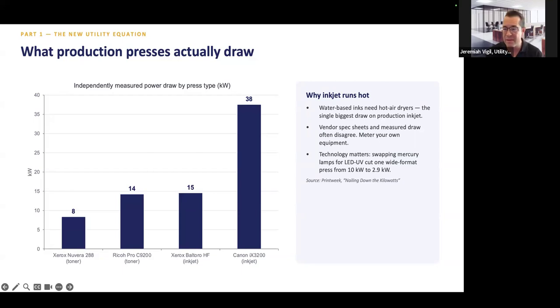On the right side, we have inkjet ones, a Xerox and a Canon. The Canon, based on the type of machine, is pulling more than double what the Xerox or even the toner machines like the Ricoh and the Nuvera pull. So technology matters—when you're swapping technology, it's really important to look at the spec sheets and see how this is going to affect your meter at the utility level and your utility bill.